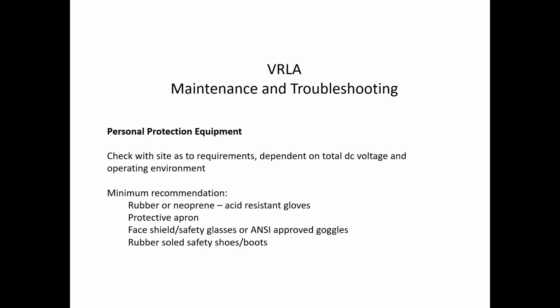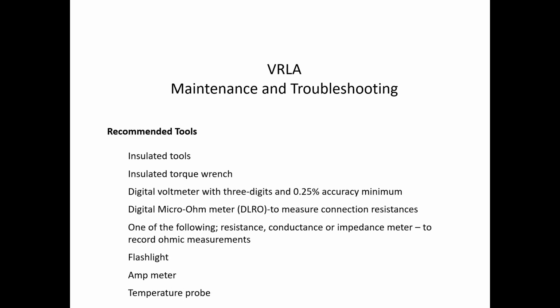PPE, sure, you have your own standards as to what technicians are required to wear when they're out servicing the batteries. The total DC voltage is also going to drive that. You could have a nominal emergency lighting battery that's 24 volts, or you could have a 480 volt UPS or 120 volt switchgear battery that's going to require a different level of protection. This is our minimum recommendations. Safety glasses and/or a shield are paramount, as well as gloves. And then hard hats and hearing protection are going to be environment driven.